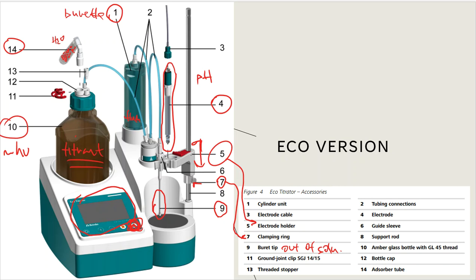And when it gets finished, it will say, clean the electrode, submerge it into your next buffer, and then hit enter or play again. So just follow the directions on the screen, clean it first, and then lower it into your second buffer, then hit the button that it tells you to hit. You never have to key in buffer of 4, buffer of 7, or buffer of 10. It knows what it should be based on the millivolt that it's reading from that solution that you have put on to that probe.